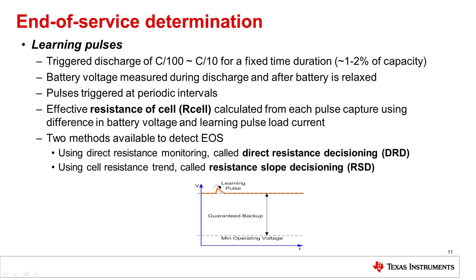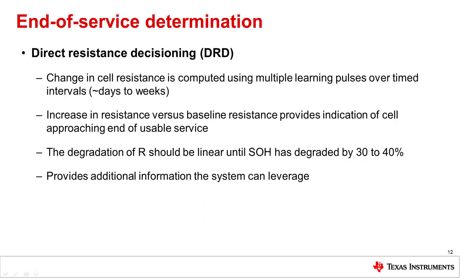There are two methods integrated into the device to trigger an end-of-service based on the collected data. One is called Direct Resistance Decisioning, or DRD, and the other looks at the trend of resistances over time, called Resistance Slope Decisioning, or RSD. The DRD approach looks at each of the R cell values calculated during operation — once a month or once every few weeks — and compares them to an initial R cell value captured right when the device was first put into operation when the cell was fresh and unaged. Based on that comparison, it can decide whether the cell is approaching the end of its life and can provide alerts.